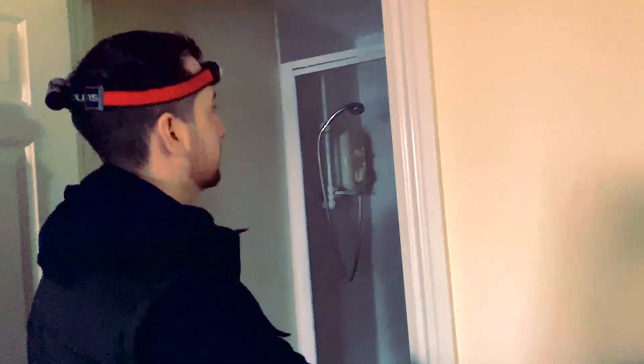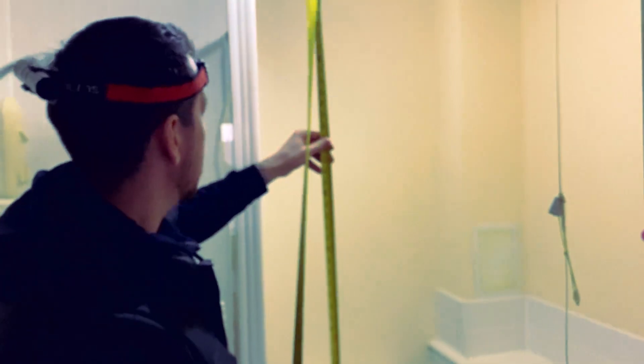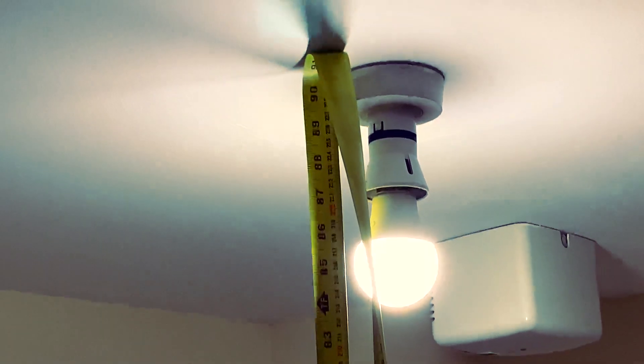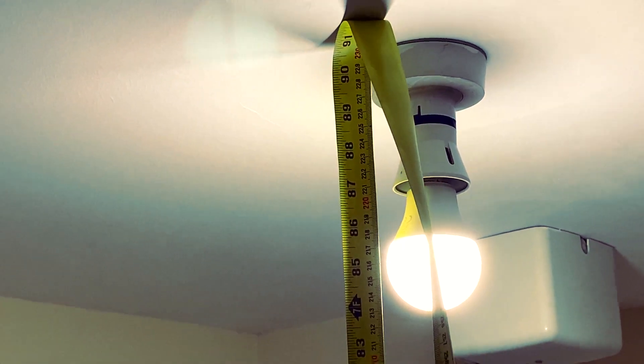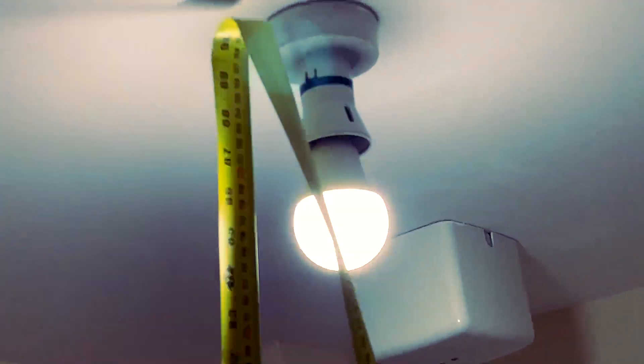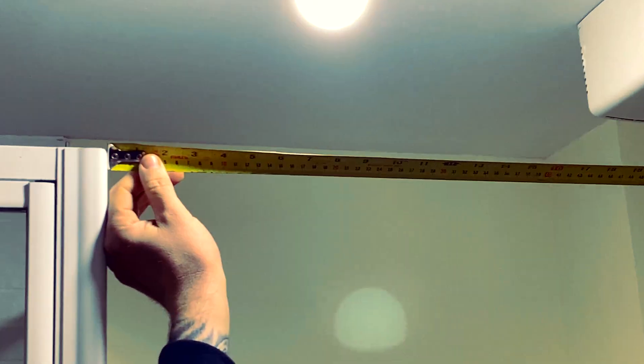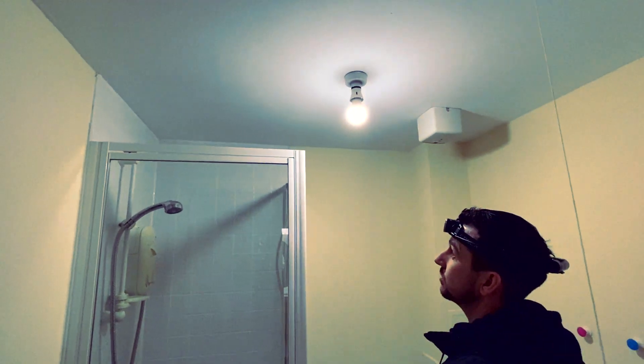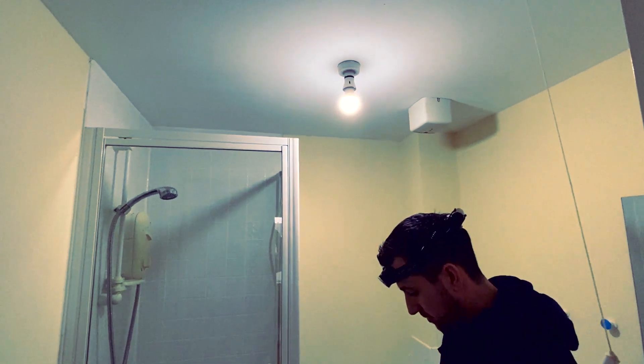This is the ensuite — same again, light switch is upside down. We'll measure this one; should be the same height as the ceiling's all the same. That light needs to be IP rated as well — it's directly in Zone 2. It's within 600 millimetres of the shower screen, so it doesn't matter that it's behind the screen and you can't touch it. It's still in Zone 2, so it needs to be IP rated.